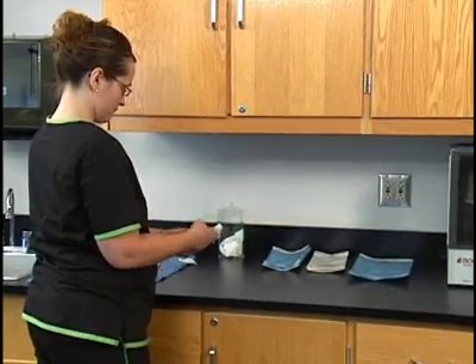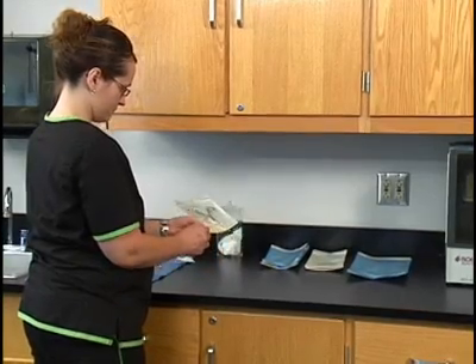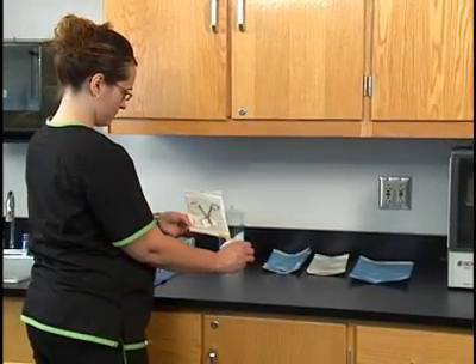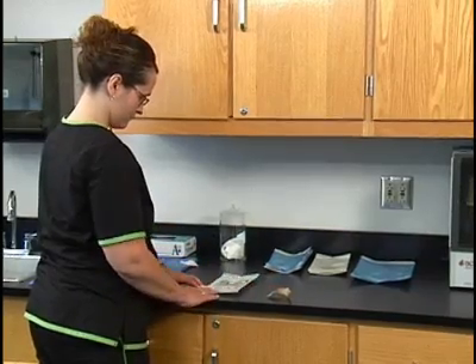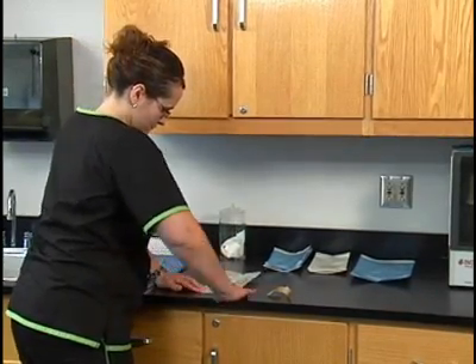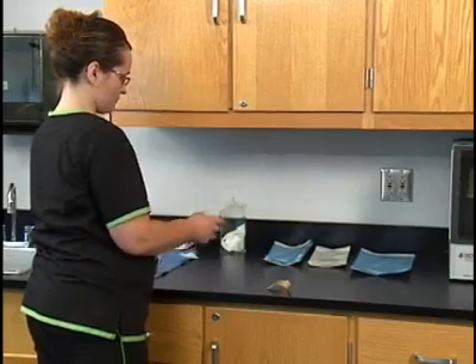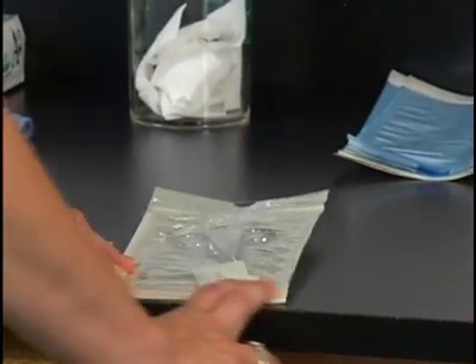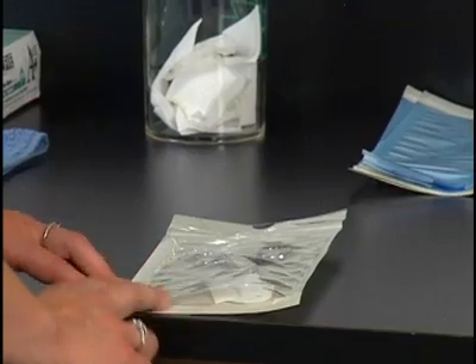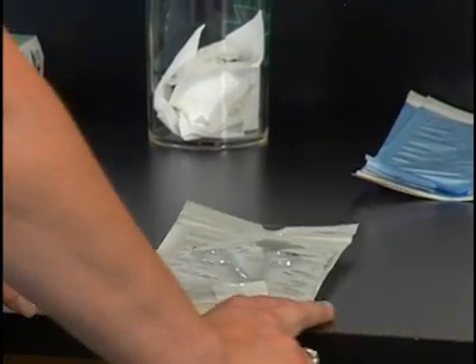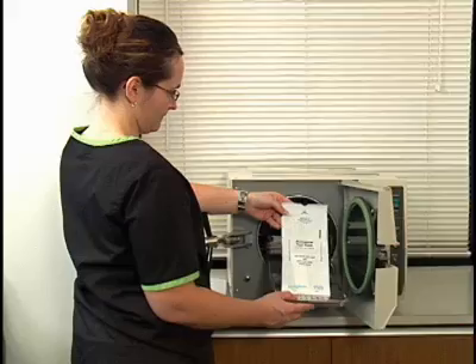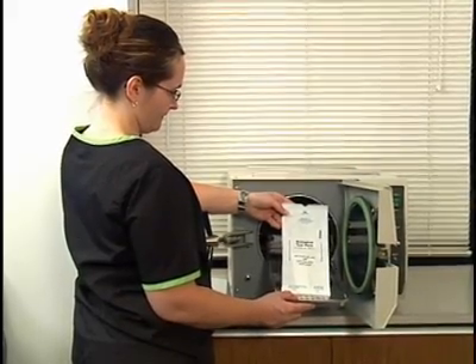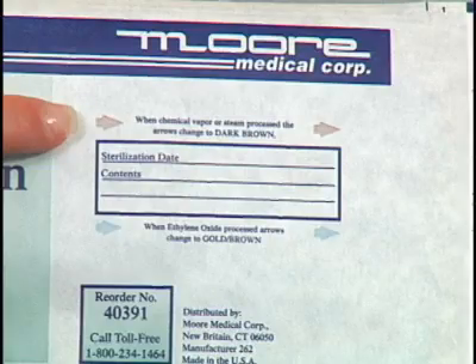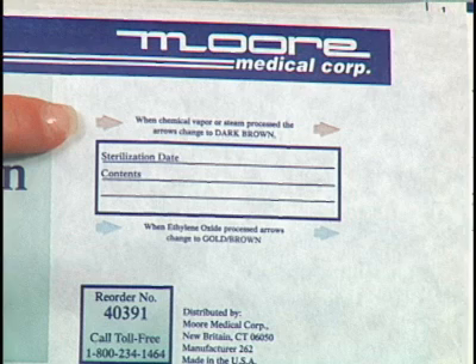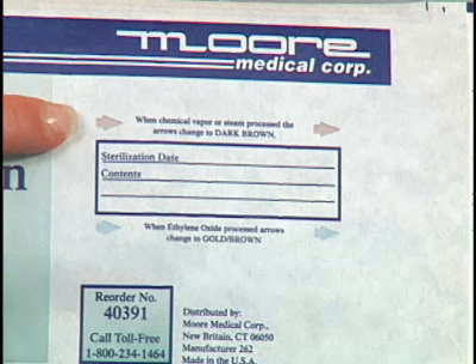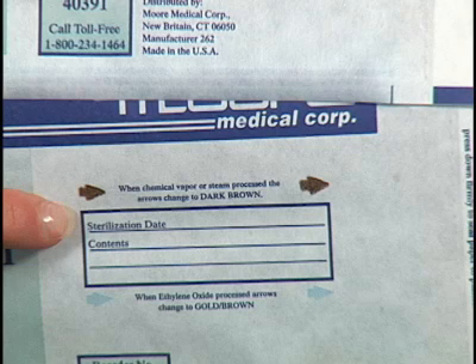Seal the open pack. Peel off the paper strip located above the perforation to expose the adhesive. Fold along the perforation and press firmly to seal the paper to the plastic. Make certain that the seal is secure by running your fingers back and forth on both sides of the pouch over the entire sealing area. Sterilize the pack in the autoclave. Most pouches have a sterilization indicator on the outside of the pouch. Make sure the indicator has changed appropriately when you remove the pack from the autoclave.